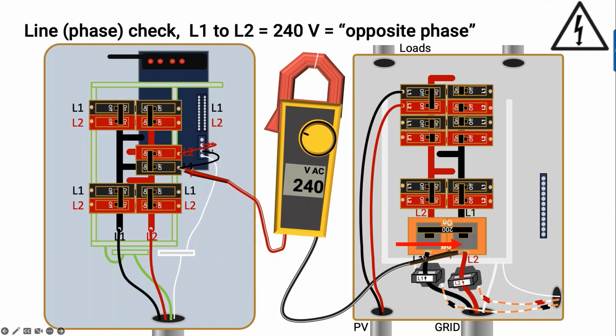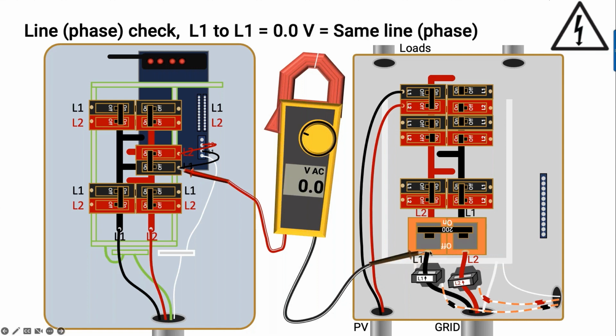All right, and this is a trick that helps you quickly identify if you've got cross phases. Here's a best practice. This is a way to identify this every time. For every installation, we strongly encourage installers to do this phase check to make sure you don't have cross phases through the system. Okay, so make sure you've got 0 volts when you go from where your line 1 CT is, that wire onto your main lug, all the way to the Envoy breakers, or even right at the Envoy terminal block, right? That should be 0 volts.